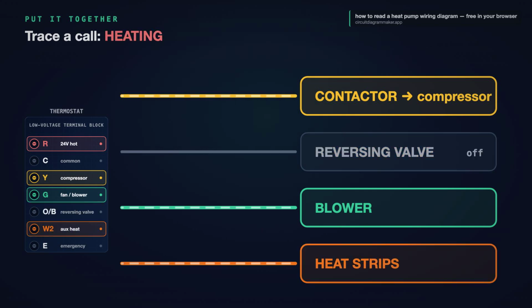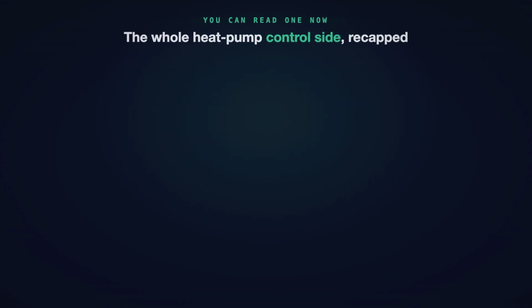R to Y and R to G again, but O is off, so the valve rests in its heating position. If it gets cold enough, R to W2 brings the heat strips in to help. And every so often, the defrost board interrupts to clear the coil. That is the whole logic: thermostat to terminal block to contactor, reversing valve, and defrost board. Low voltage commanding high voltage every single time.